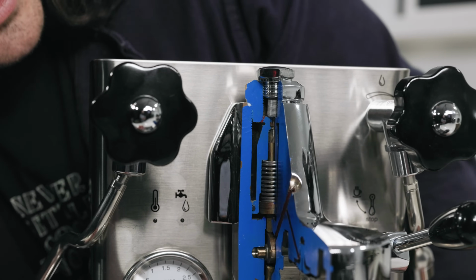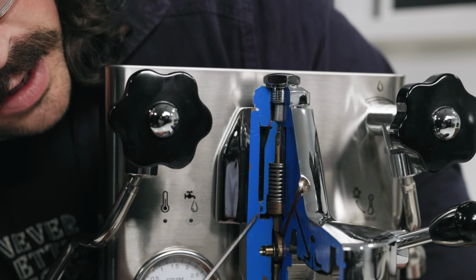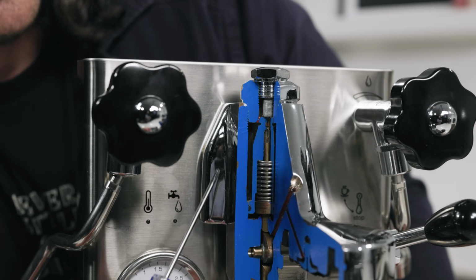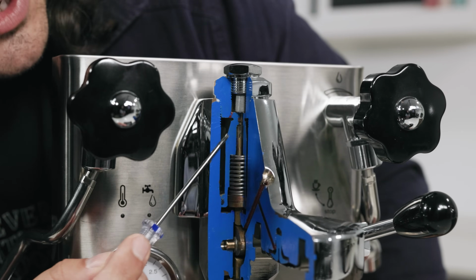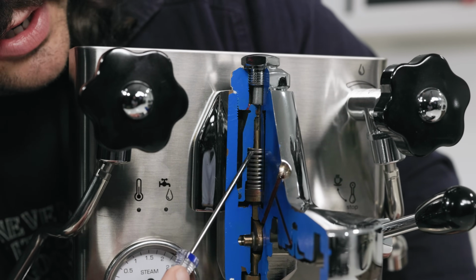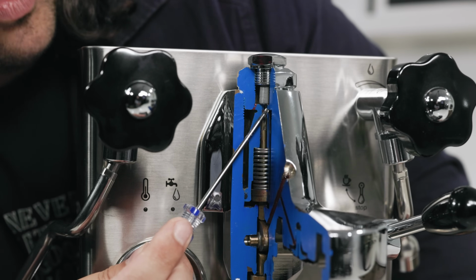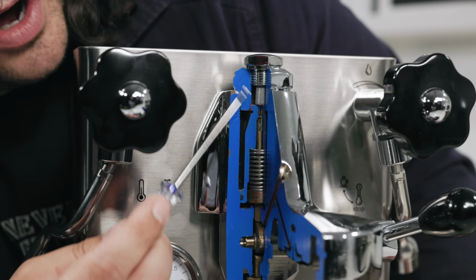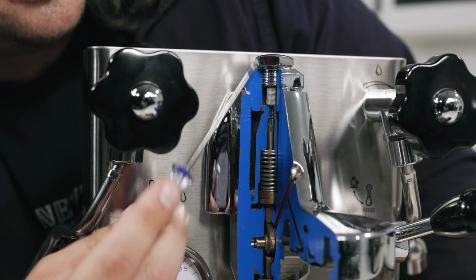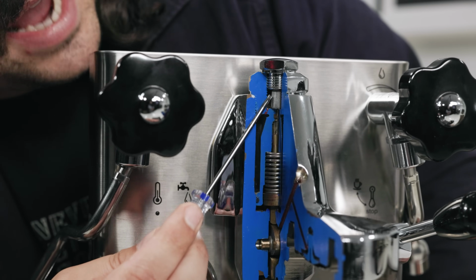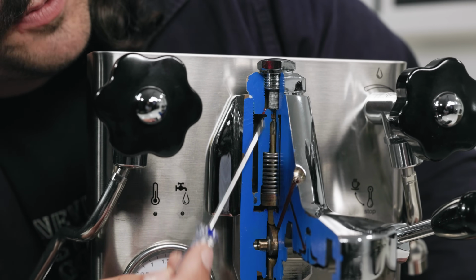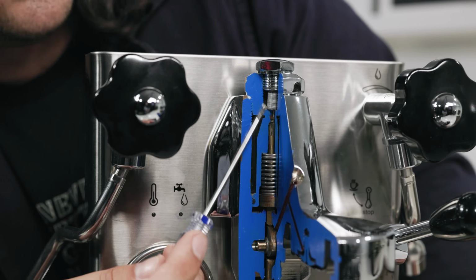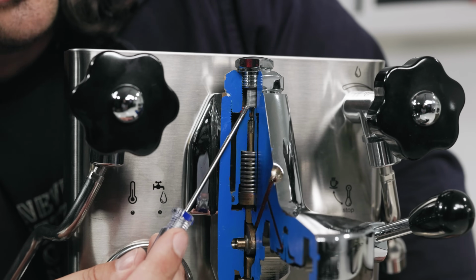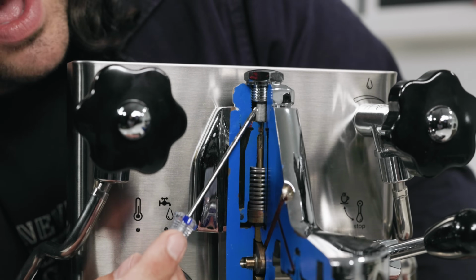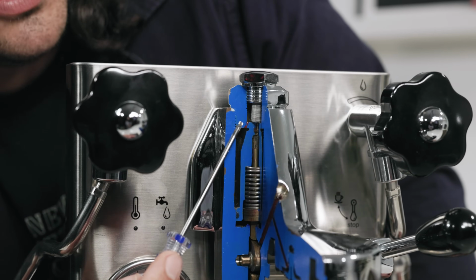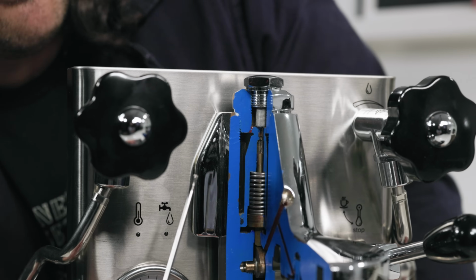So as you see, once we have actuated that lever, this valve opens up here and water is now being highly pressurized because the pump has been actuated. So the water in this chamber here is now pressurized and it starts to try to release up here. There are holes surrounding this that allow small amounts of water to fill the chamber up here below what's called the mushroom cap. So water comes into this area and then there's only one exit. Since pressure is pushing up, that water cannot leave those holes again because it's being forced through the holes. So because there's nowhere for that to leave, there is only one hole that the water can escape into, and that is called the gicleur. It is typically 0.6 millimeters.